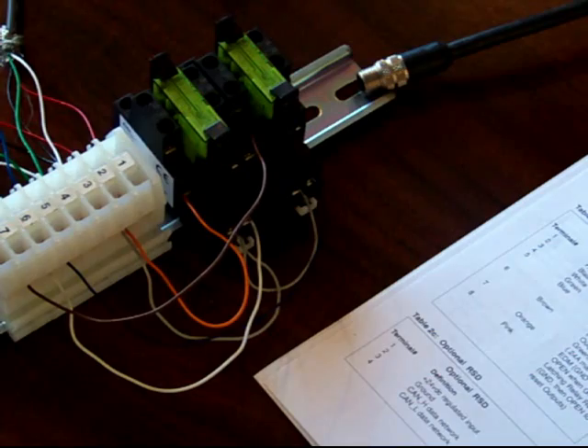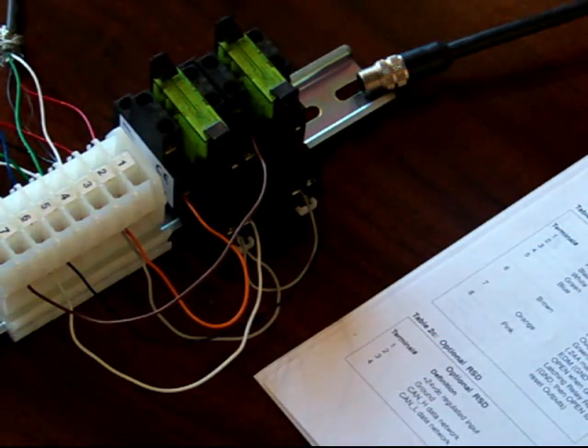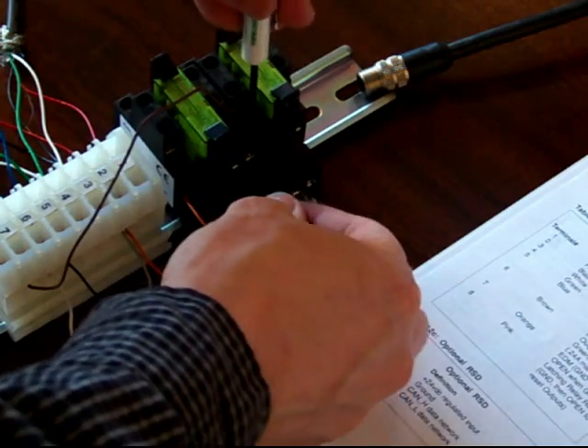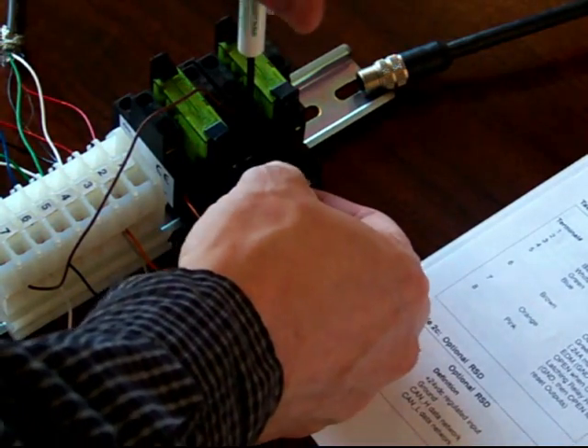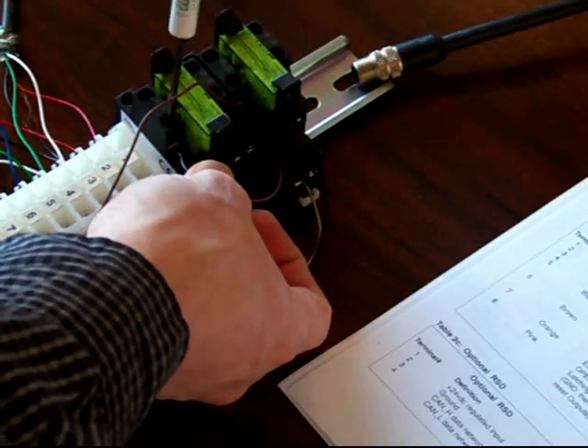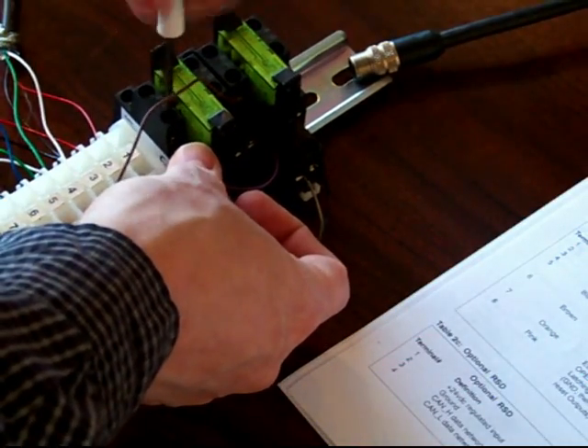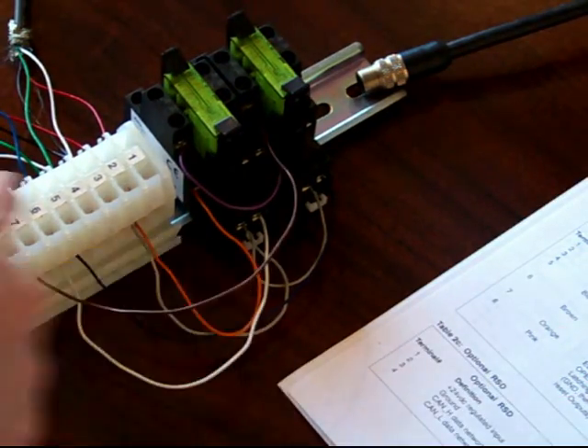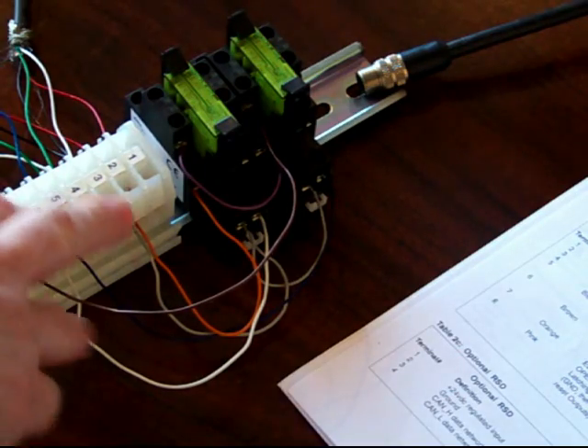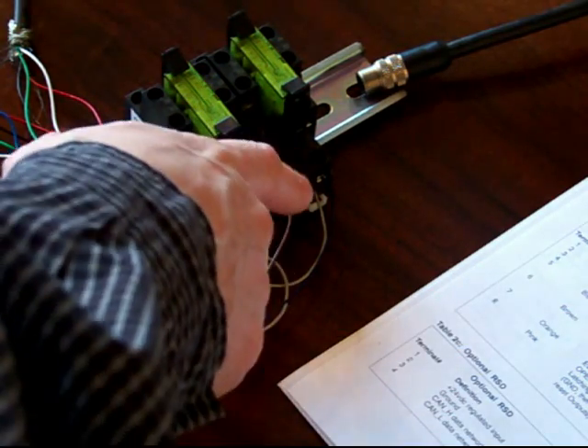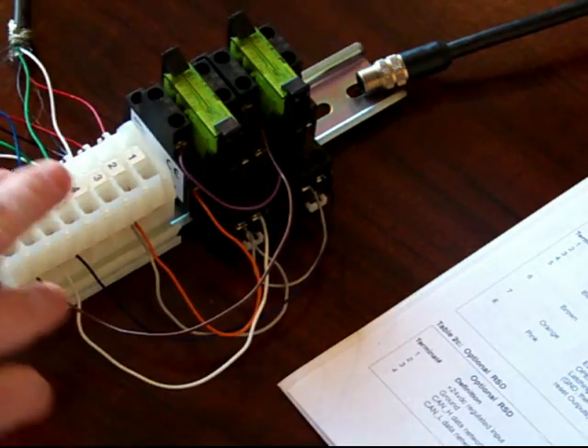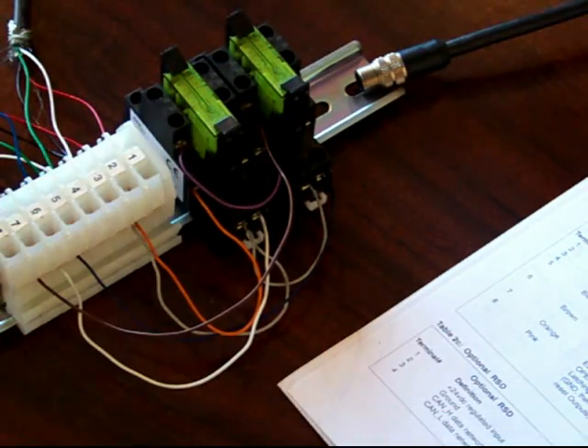Now we need a wire to go from 11 to 12 between the two safety relays. We now have the orange wire, terminal 7, passing through the normally closed contact of both safety relays in series and back to ground.